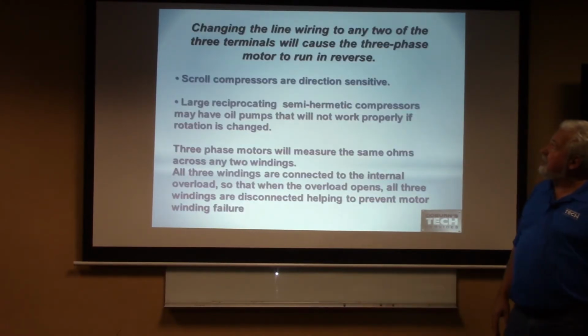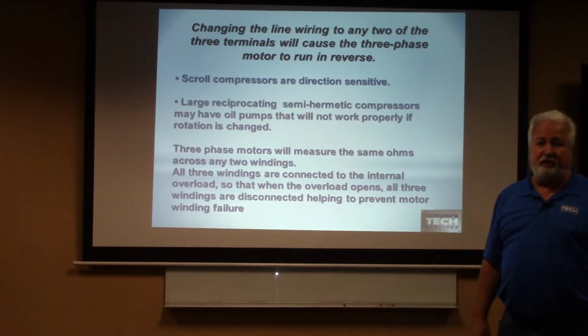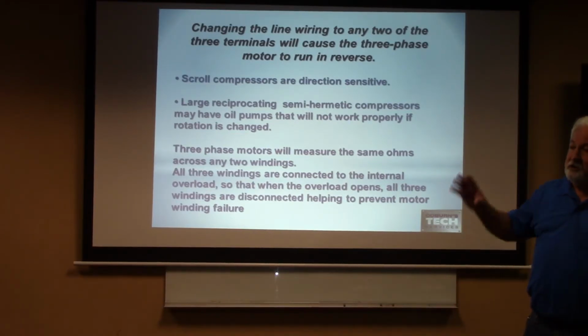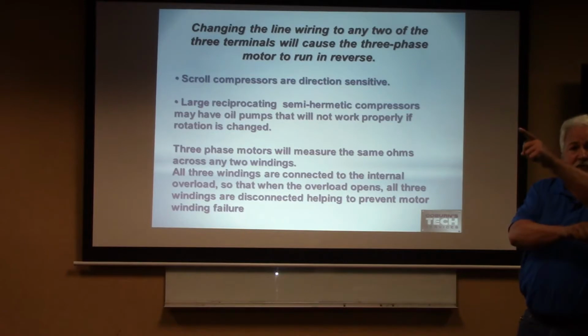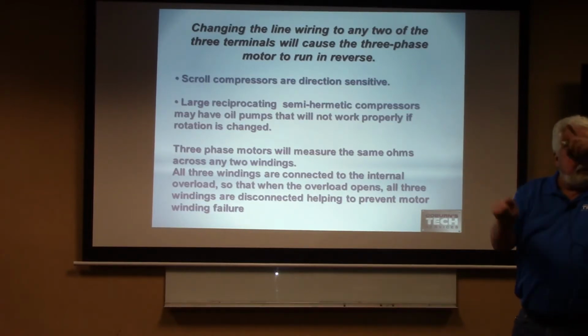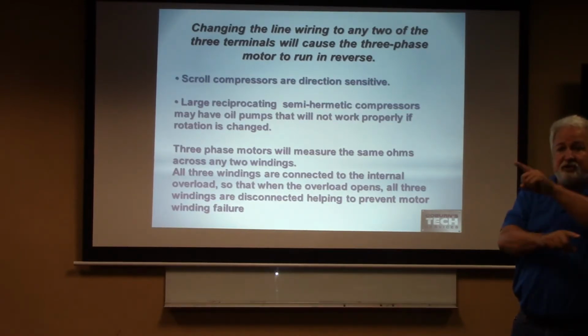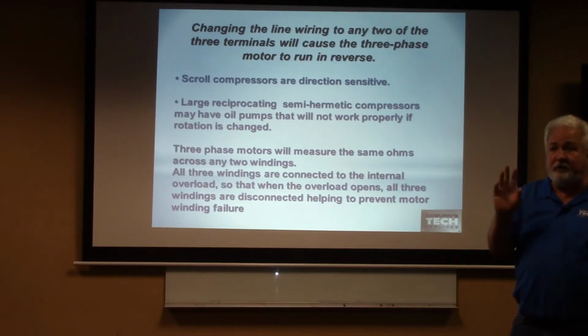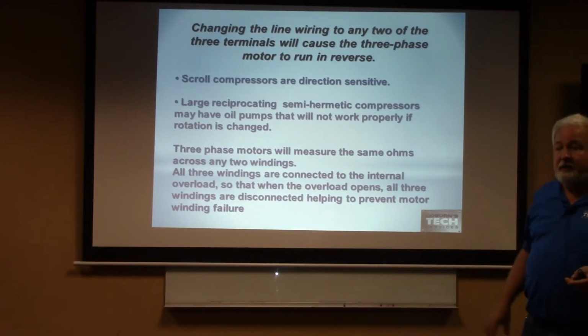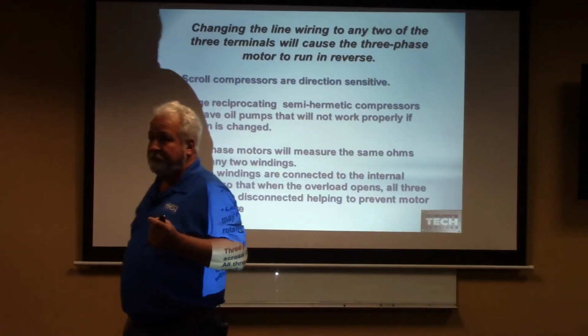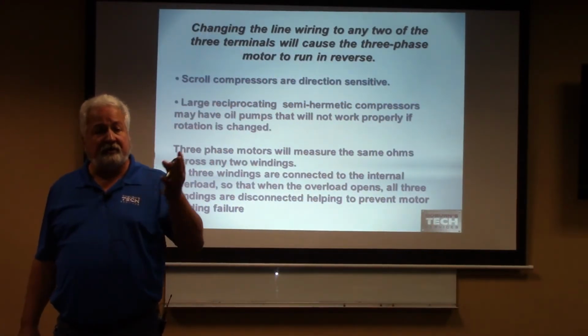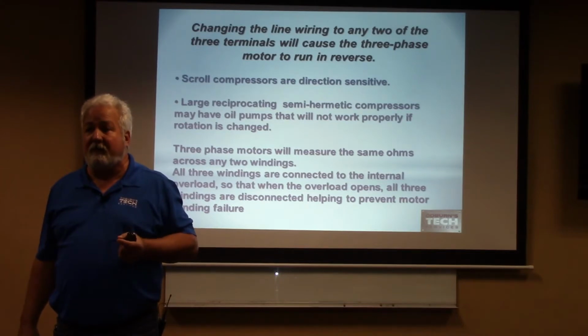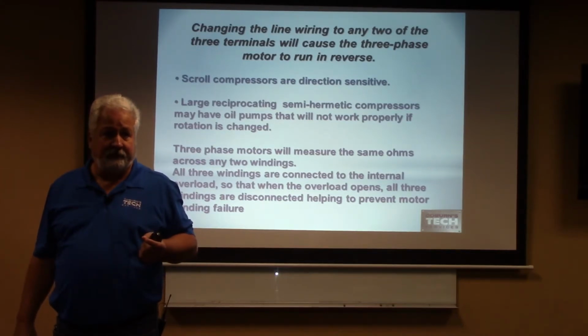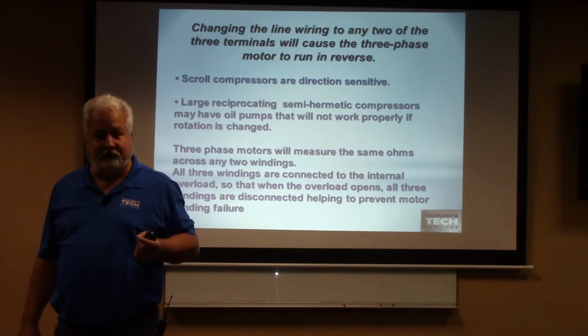Changing the line wiring to any 2 of the 3 is going to change the direction of that motor. So if I change line 1 to line 2, line 2 to line 3, line 1 to line 3, if I change any 2 of those wires around, I'm going to change the direction of the motor. That's fine as long as I'm not dealing with a scroll compressor. If the scroll compressor gets changed, it's going to start running backwards. And what does that sound like? Like nails. It sounds like rocks inside that compressor.